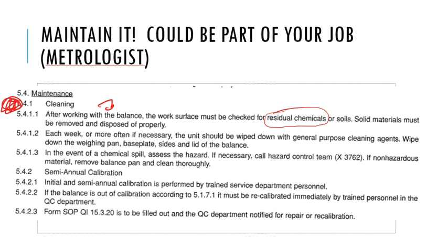So 5.4.1.2 for this particular SOP. For this company, it says each week the unit should be wiped down with general purpose cleaning agents, and sometimes that can be as simple as water or some type of alcohol. Then it says wipe down the pan, wipe down the base plate, and wipe down the sides and the lid of the balance. And I'll show you where those things are in just a second.